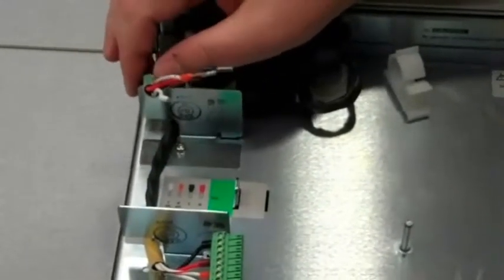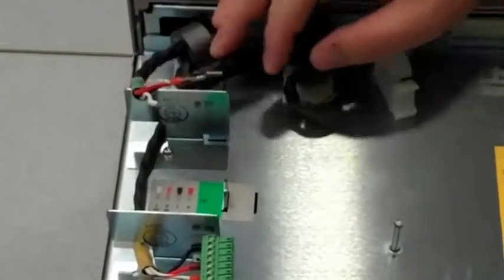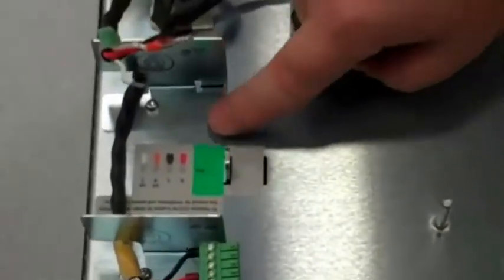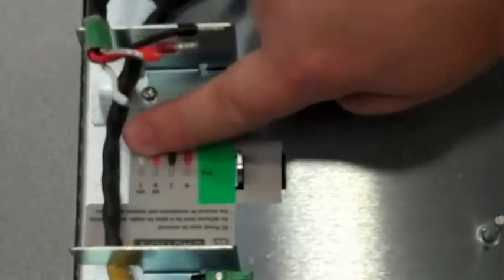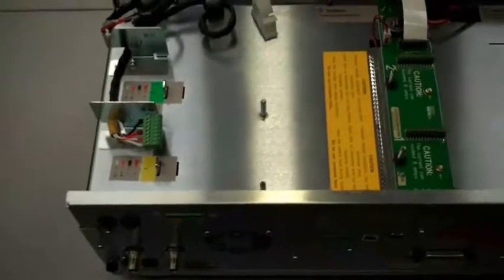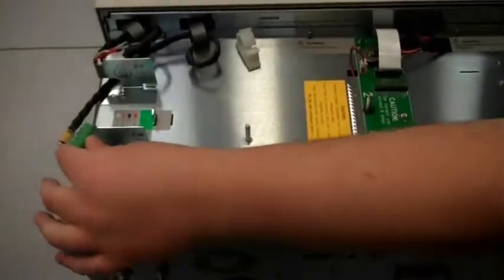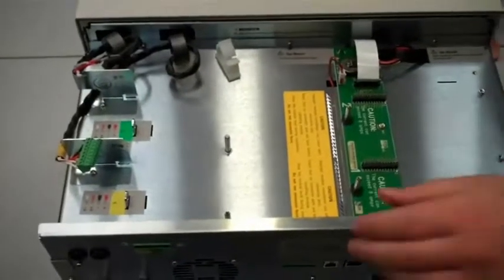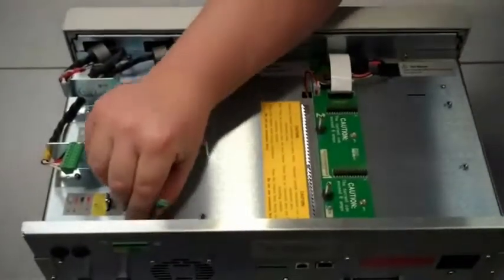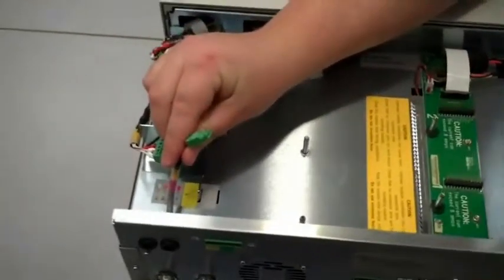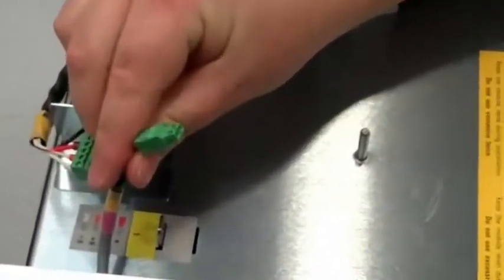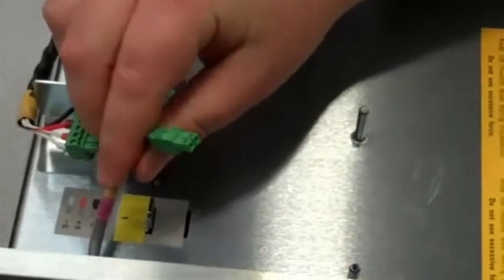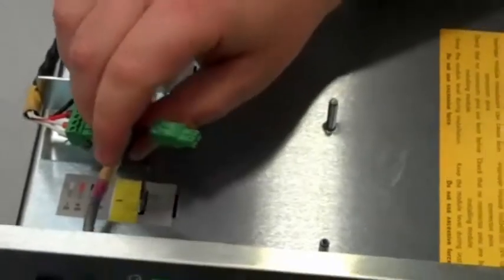The wires are all color coded and the key to the color coding is located on the label right there. You just match that up to the label on the rear of the module and it shouldn't be much trouble at all putting the connector on. You can see here's one with the connector on in channel one. The other thing we have are these connectors that connect to the auxiliary measurement on the N6781A module that take that port out to the back rear panel of the unit that we showed earlier.